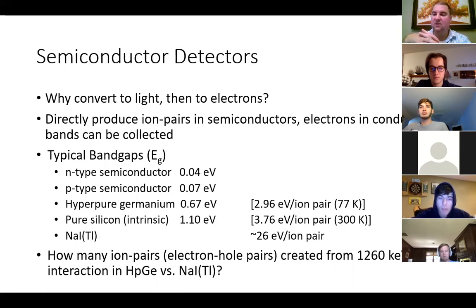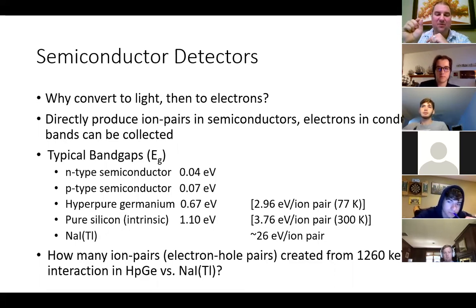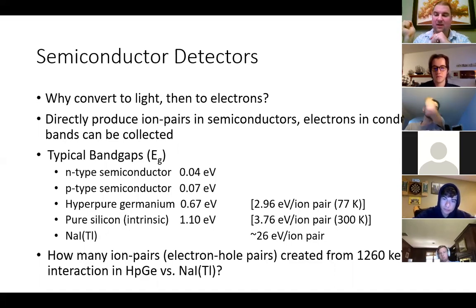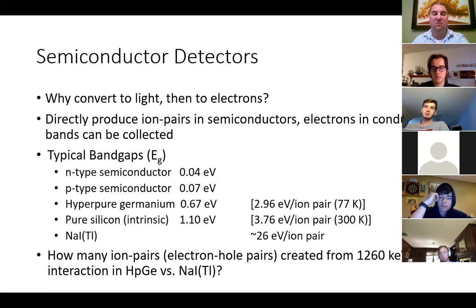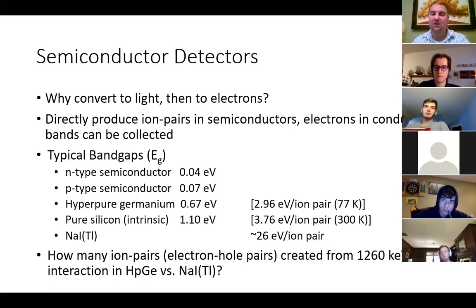Germanium detectors require liquid nitrogen, operating at 77 K where it takes just under 3 eV to create a collectible ion pair. Silicon at room temperature requires 3.76 eV per ion pair and can generally be operated without cooling. Hyperpure germanium must be cooled; at room temperature, thermal promotion of electrons via the Boltzmann distribution fills the conduction band with too many thermally-excited charge carriers, making the detector non-functional.